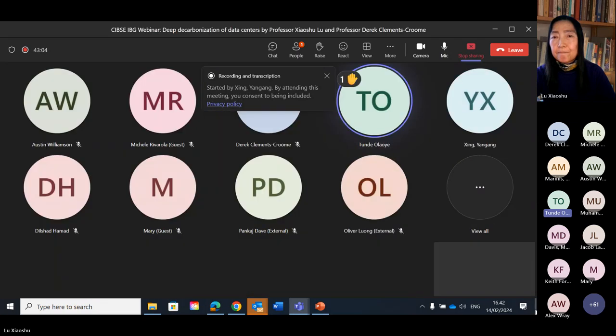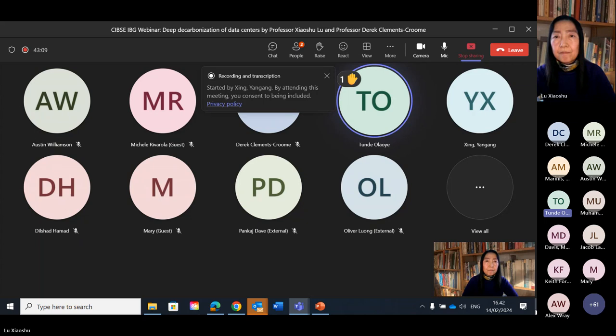Just wanted to ask a question about a comment you made there about heat recovery from the data centers doesn't need heat pumps. On a typical 3G network, obviously flow temperatures are going to be 65 plus. How do you envisage we can recover heat into those type of networks at such high flow and return temperatures without a heat pump?